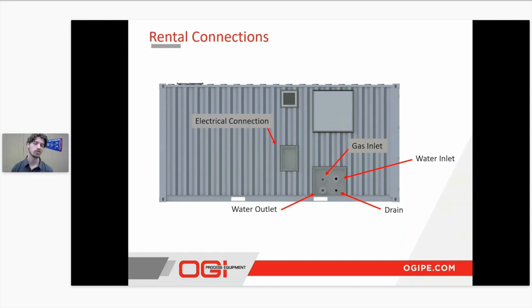Each QuikWater rental is going to include startup by an OGI technician on site. With that startup, we're going to be coming out, checking out the unit, and making sure that everything is plugged in correctly. We'll verify your site emissions, as well as bleed the burner, and make sure everything is the same as when it left our facility. And then we run a safety deployment check on every single safety on our QuikWater, re-verifying everything. With all of our rentals, we do the same back testing procedure that we do here at OGI on each QuikWater that leaves our facility brand new.